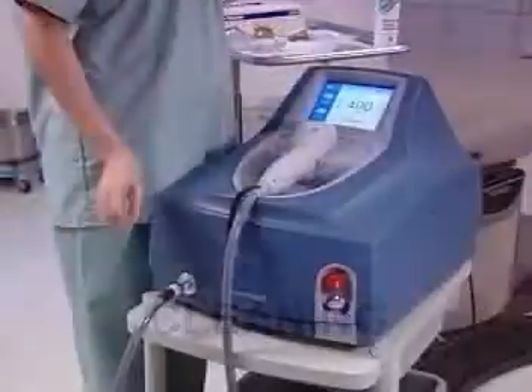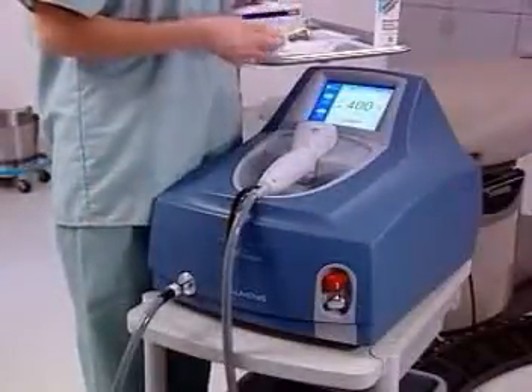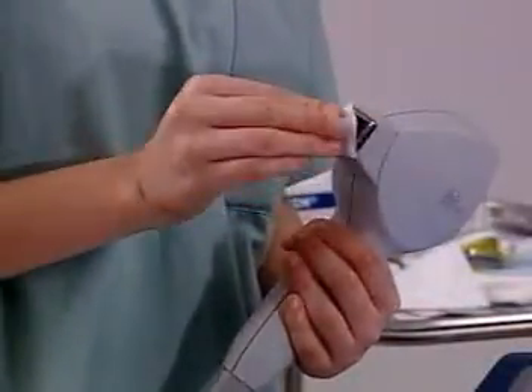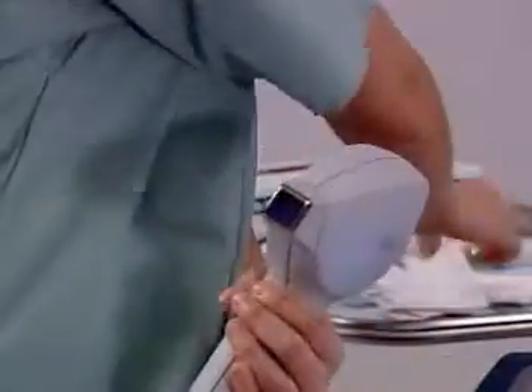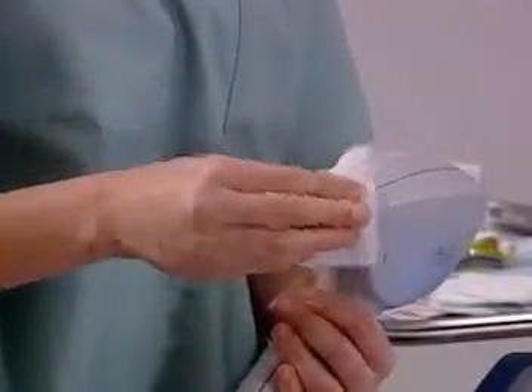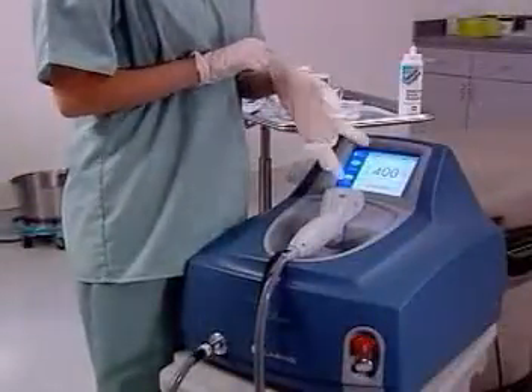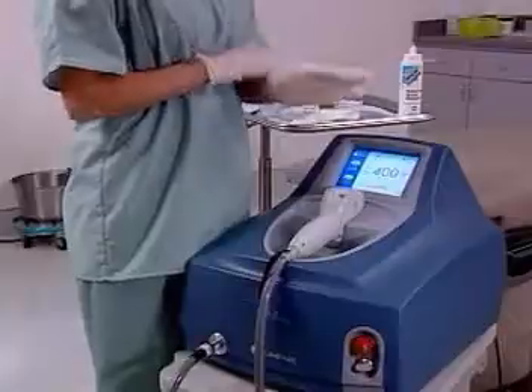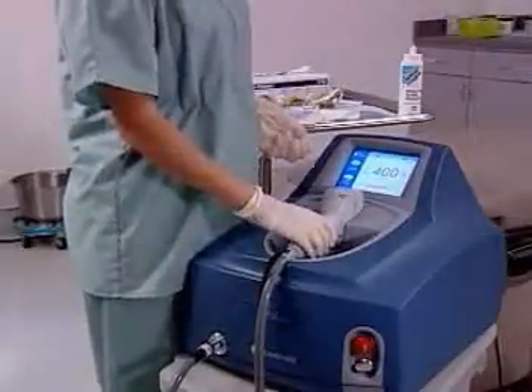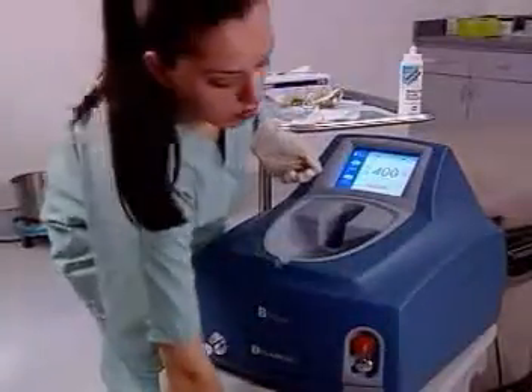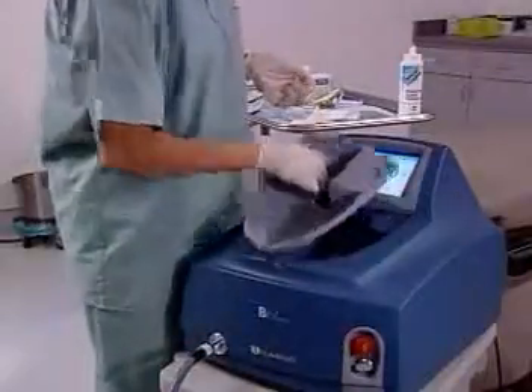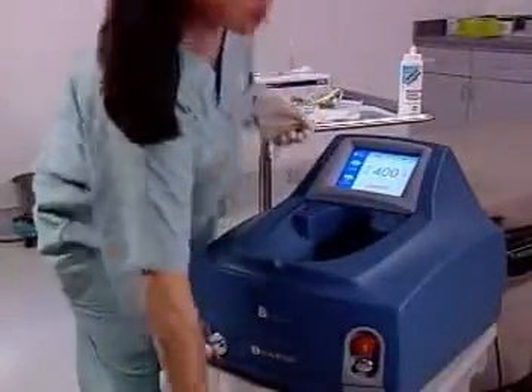The handpiece tip can be cleaned with alcohol, Cavicide, or Virex. Apply cleaning solution to a clean gauze pad, soft cloth, or use an alcohol pad to wipe the handpiece tip. Use a separate piece of clean cloth to remove any residue left by the cleaning solution. You should wear gloves when cleaning the protective window above the energy meter, as fingerprints and smudges can affect calibration readings. Remove the calibration storage port insert.